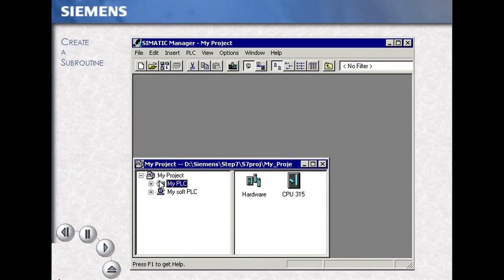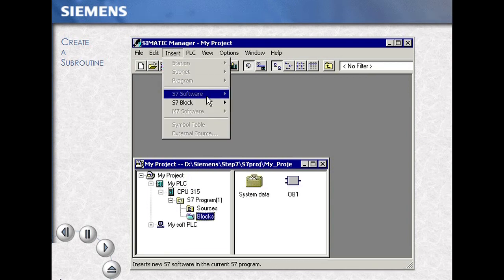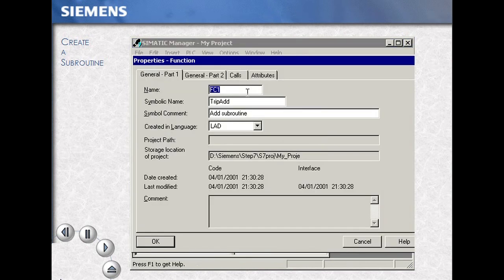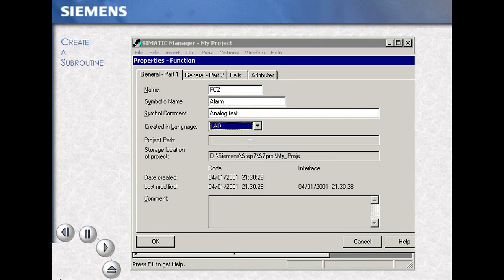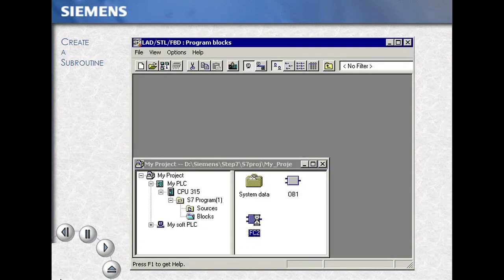Open your station to your program folder, then select the blocks folder. Using the menu items Insert S7 Block, we select Function, a subroutine. We select the names as we choose — Symbol Names, Symbol Comments, and Programming Language for our example ladder — then we OK. Double click opens that block into the program editor.